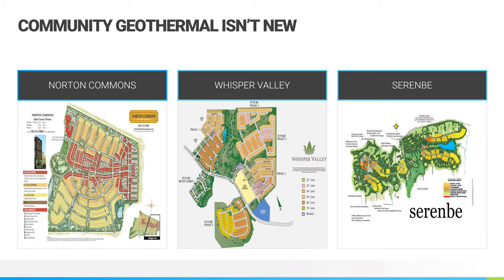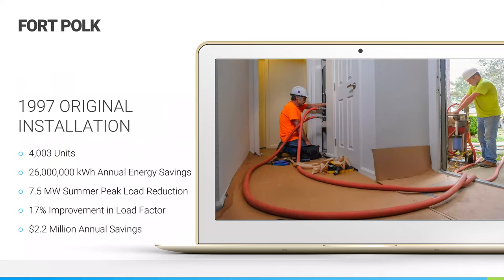But these are all recent developments. Going back even as far as '97, the Fort Polk installation in Louisiana had over 4,003 military units. One of the unique things here is you can see the dramatic energy and peak load reductions. Because of the peak load and load factor, they were actually able to negotiate with the utility a better rate structure because of the reduced demand this would bring in versus a traditional air source system.